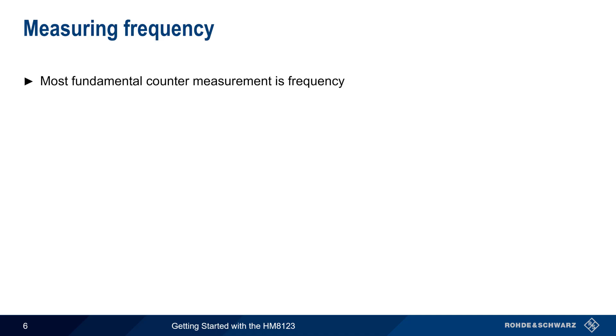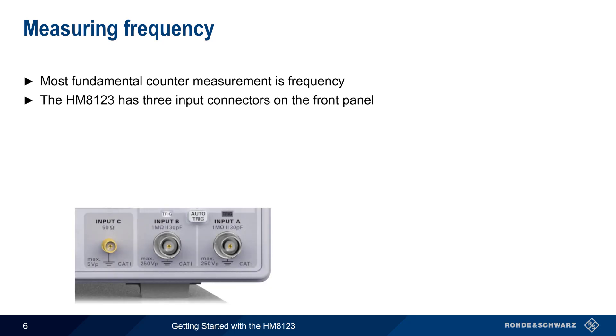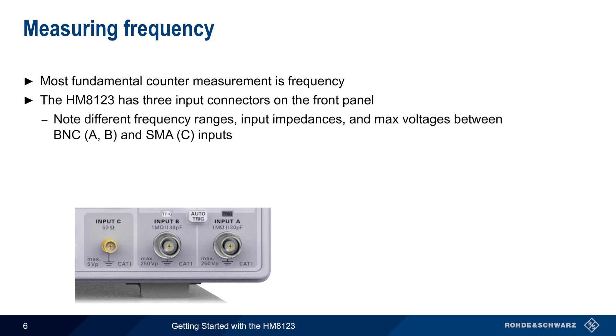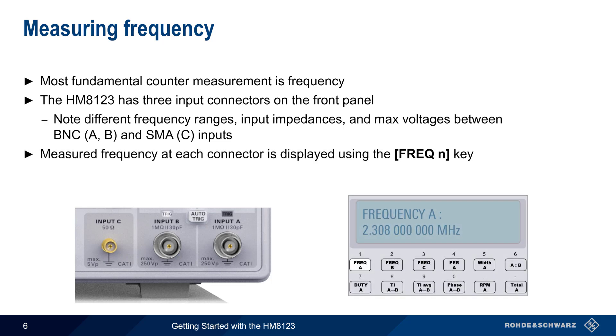The most fundamental counter measurement is frequency, and this can be measured on each of the three front input panel connectors of the HM8123. Note that the two BNC connectors for input A and B, and the SMA connector for input C, have different frequency ranges and maximum voltages. And the input impedance of C is fixed at 50 ohms. The measured frequency at each connector can be displayed by pressing the corresponding frequency key, for example, frequency A, to see the frequency on channel A. Note that only one input frequency can be displayed at a time.